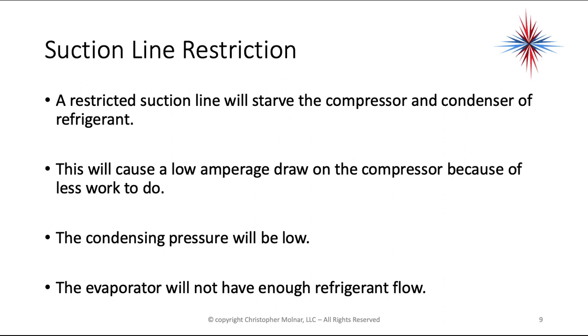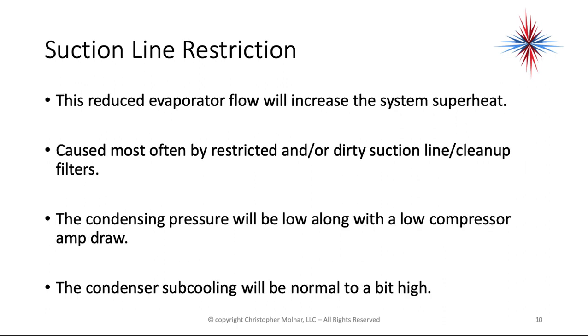The evaporator will not have enough refrigerant flow — you might think the evaporator would be fuller, but it won't. It won't have enough refrigerant flowing through it. This reduced evaporator flow will increase superheat. Remember, superheat is dependent on how fast the refrigerant is flowing through the system.